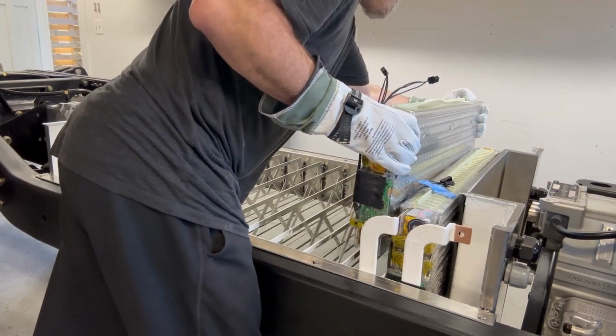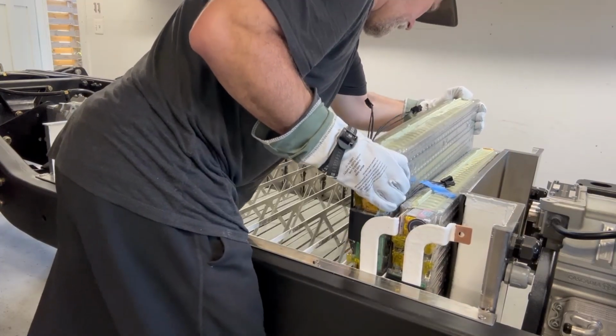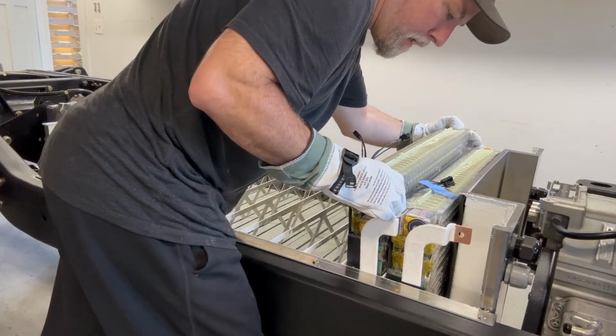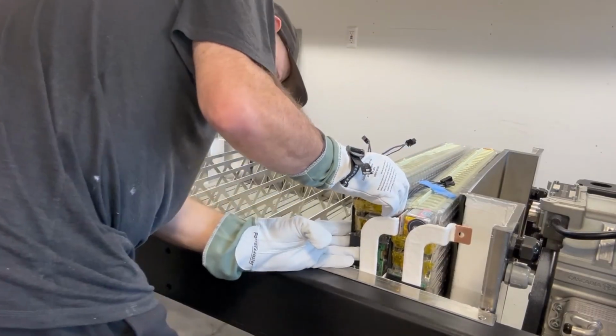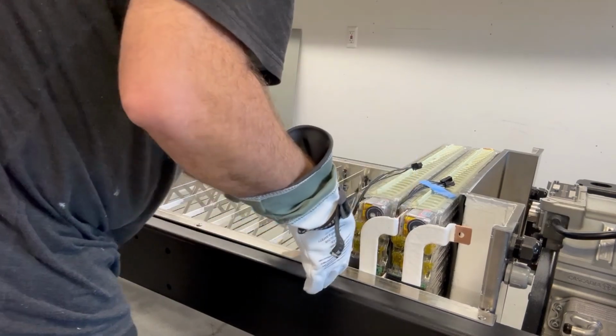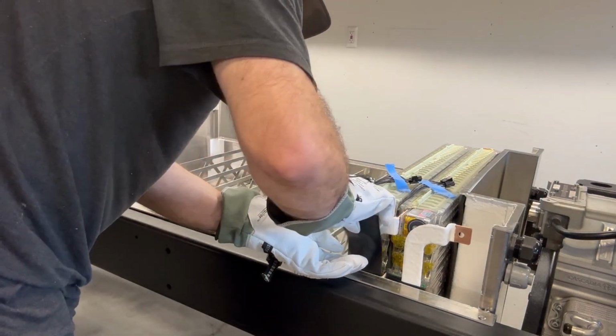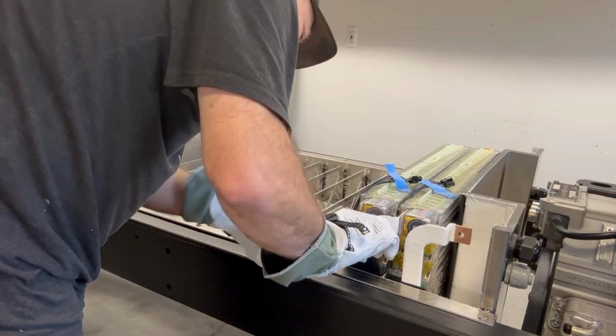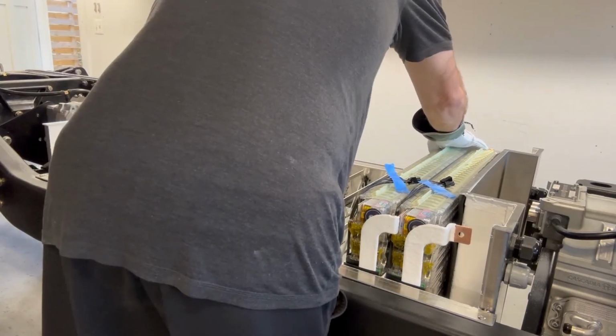Once we get to this second module, we need to use electrically insulated gloves with leather gloves over the top, since our voltage will now be adding up to a potentially deadly level. As before, we will place the rubber sheet between the box wall and the bus bar and then shift the box tight to the high voltage side.